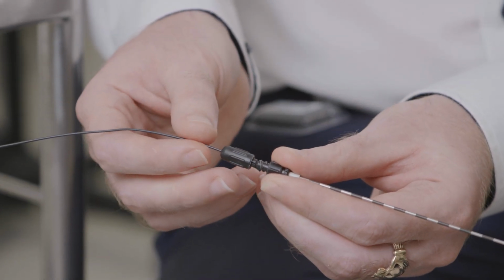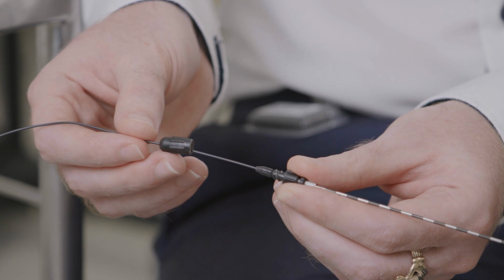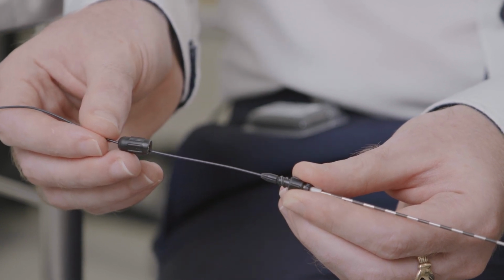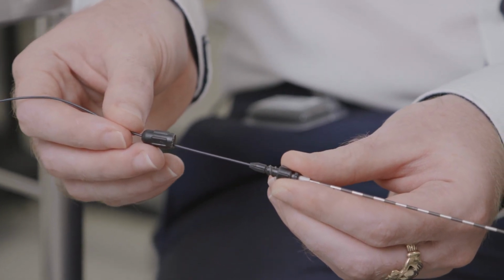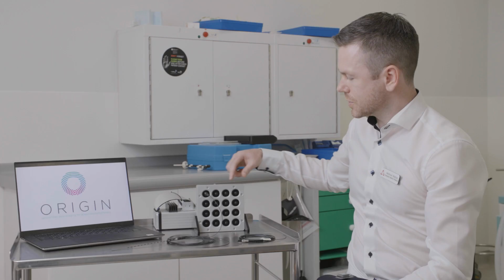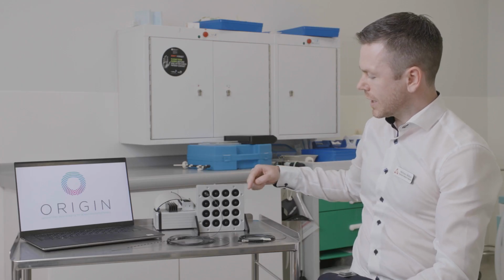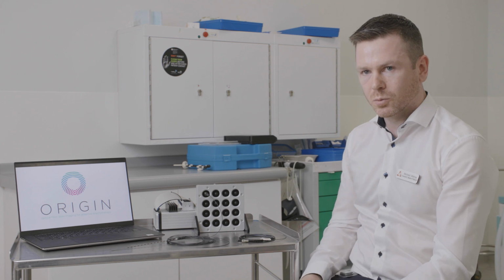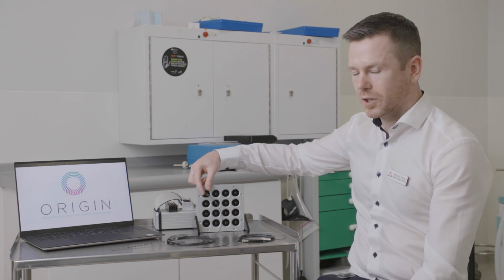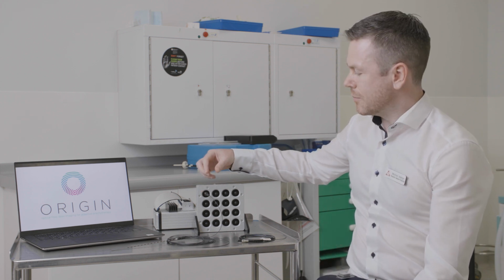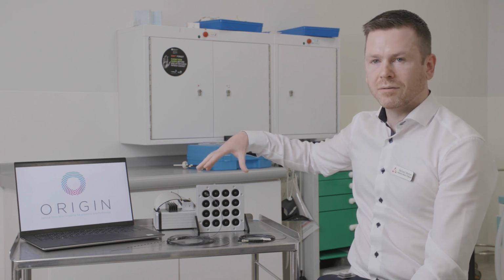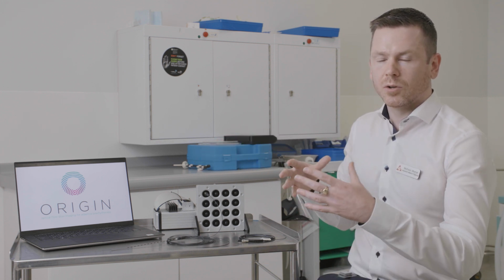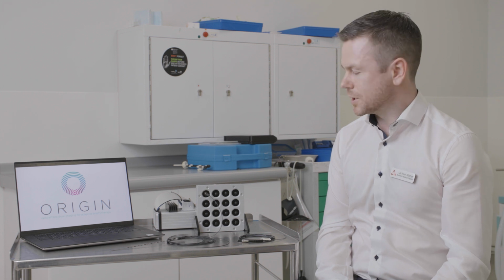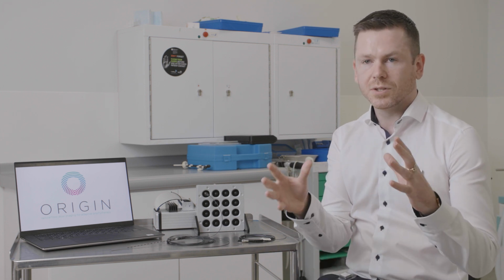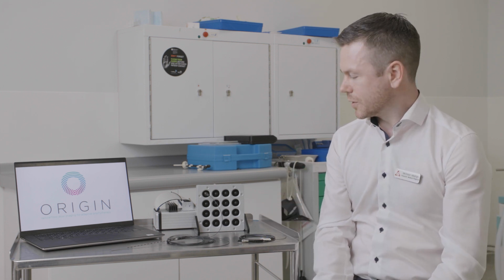When exposed to radiation, light will be emitted by the scintillator tip, which will propagate along the fibre and then travel to our detector system. So here we have a rack of 16 silicon photomultipliers. I've only connected one fibre here at the moment. But the Origin system crucially will have the ability to consider up to 16 optical fibres at a time, so we can sample many different regions of interest during a brachytherapy procedure.